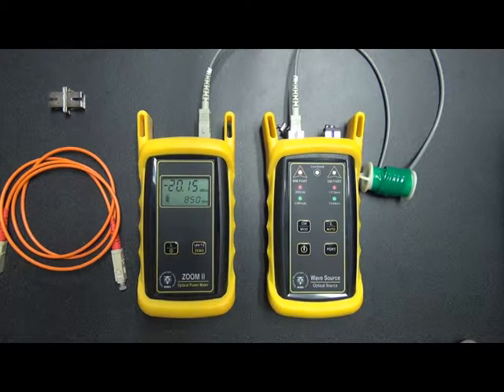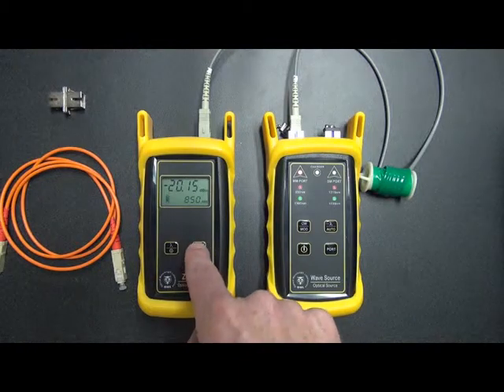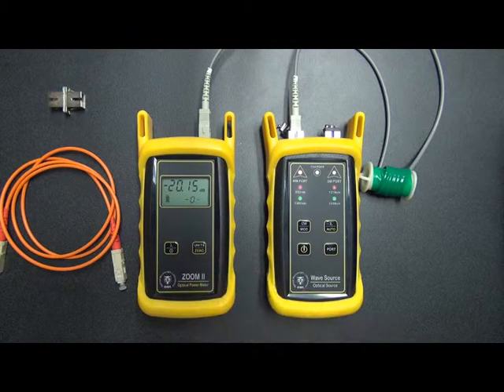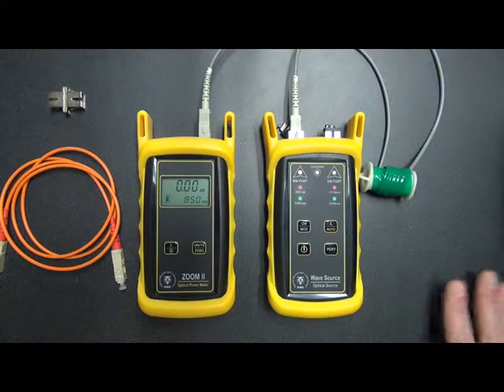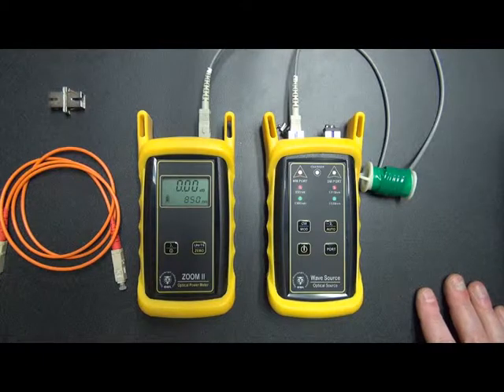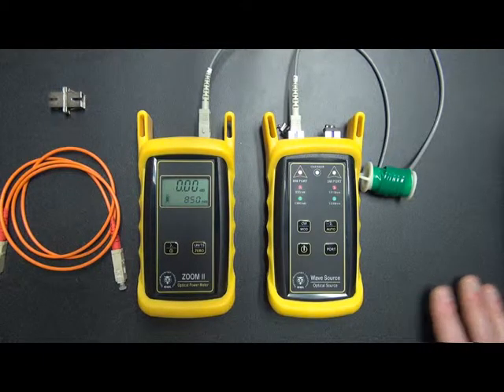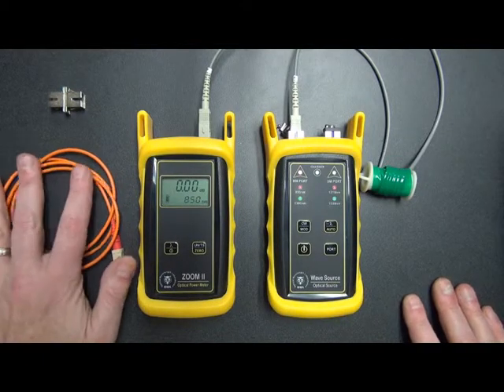Okay, notice it says minus 20.15. That's also within our specifications. It's not below minus 21. So 850 nanometers is also okay. So we can zero out this wavelength as well. All right, so now we have both wavelengths zeroed out. And this is just temporary, it's just a temporary reference. But it's zeroed out. Now we can check this cable here.